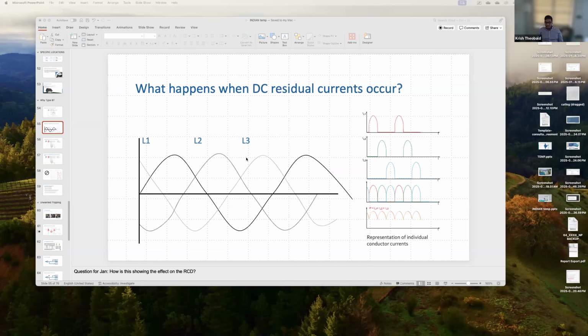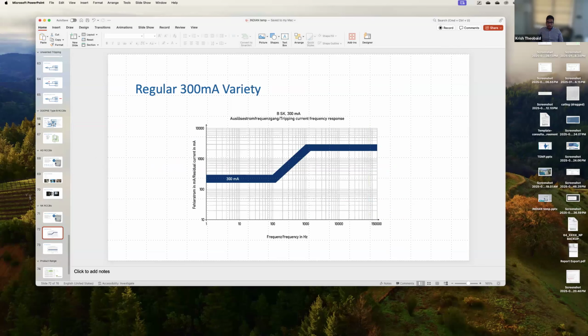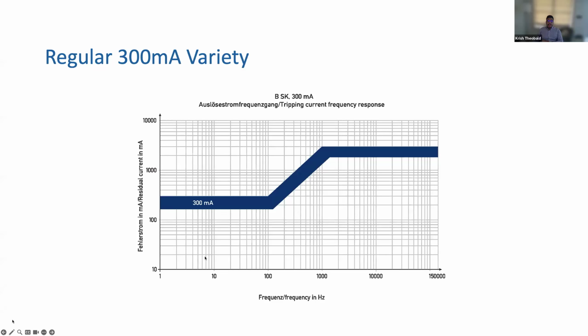This is a very good question, and it comes down to the type of residual current device. If you have harmonics in single phase, it has to be a type F. If you have harmonics in 3-phase, it has to be a type B. And it depends on the manufacturer. For example, like Gerard showed us, depending on the frequency of the harmonic current, the RCD has different tripping characteristics. It is normally the higher the current, the higher the frequency, the more time the RCD takes to trip.